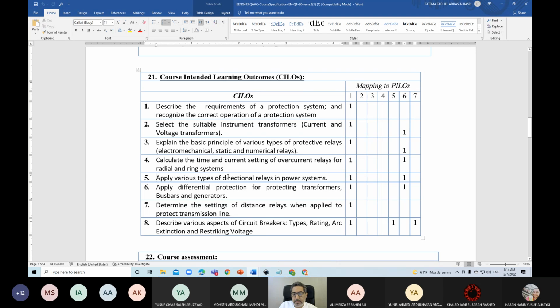Then we'll focus on directional relays. How do you protect systems that have loop systems or ring systems or parallel line systems? Okay, so we need directional relays. So how a directional relay operates, how we select the directionality. Okay, so this is a dedicated chapter on this.